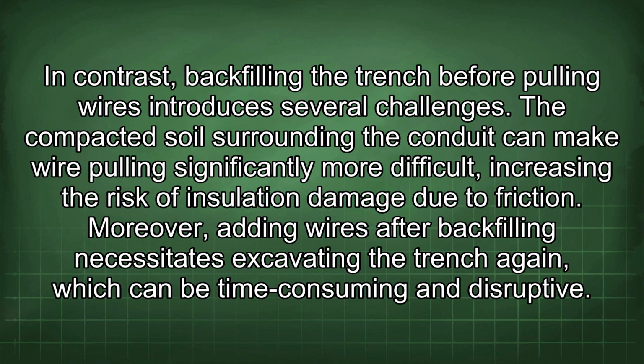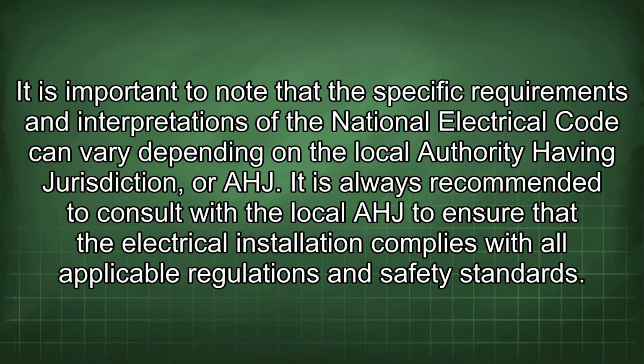With pre-existing conduit in place, adding a wire becomes a relatively simple task of pulling it through the existing raceway. In contrast, backfilling the trench before pulling wires introduces several challenges. The compacted soil surrounding the conduit can make wire pulling significantly more difficult, increasing the risk of insulation damage due to friction. Moreover, adding wires after backfilling necessitates excavating the trench again, which can be time-consuming and disruptive. It is important to note that the specific requirements and interpretations of the National Electrical Code can vary depending on the local authority having jurisdiction, or AHJ.